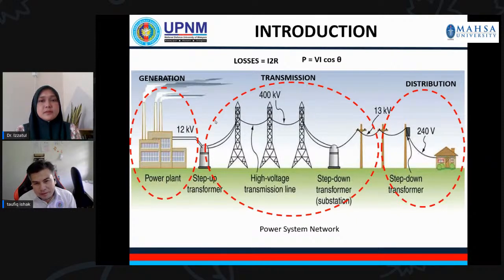All right. Another important thing: when we have small currents, we can use a smaller cable to transmit the power. That's a good thing. When you have a smaller cable, you do not need a very strong structure to support the cable. However, when you increase the voltage, you need to have a very good clearance from the ground. So the higher the voltage level, the larger the clearance. That's why, as you can see from the transmission tower, the higher the voltage level, the higher the tower itself. Okay.